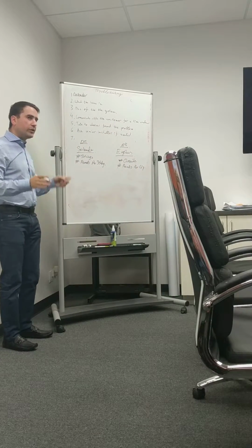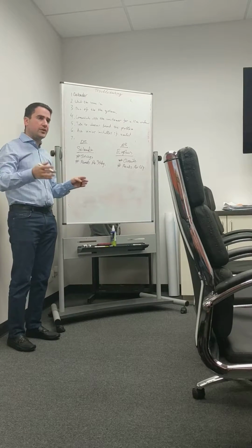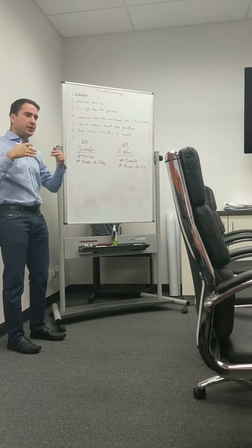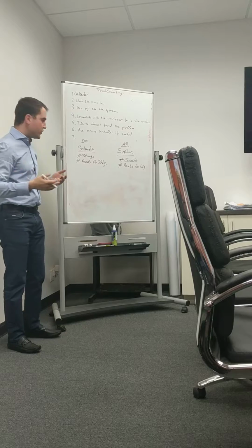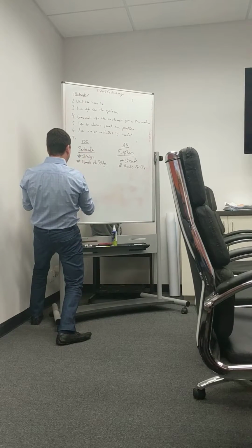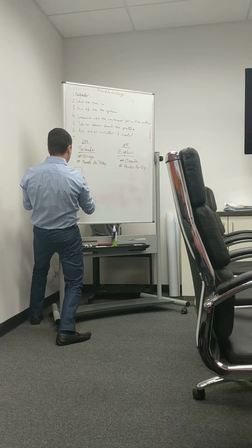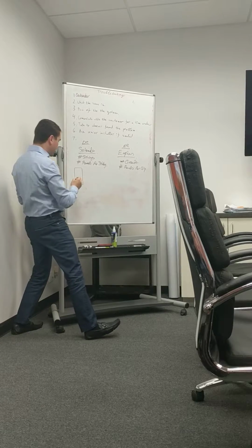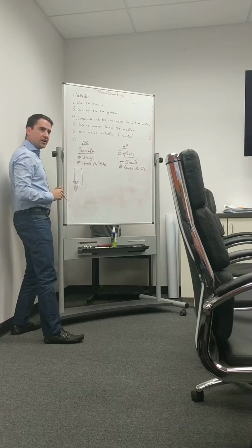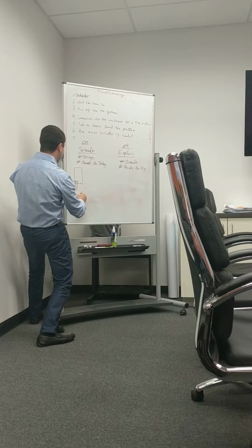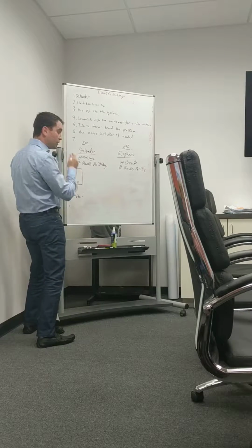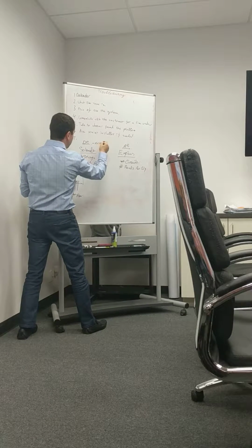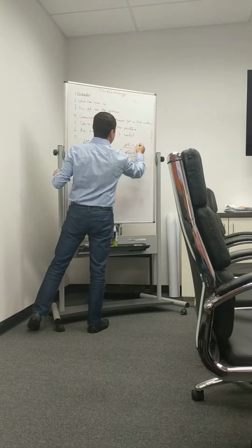Now, when you arrive to the job site and you know one panel is not performing, right? It can be an optimizer, it can be inverter, it can be microinverter, or it's a panel. So with SolarEdge, you have the inverter. In the inverter, you have the string lines coming here to the inverter. Positive, negative, positive, negative. When you know the number of panels and the number of strings, you have to measure the volts. Because it's DC, it's volts. On the AC, you measure the amps.